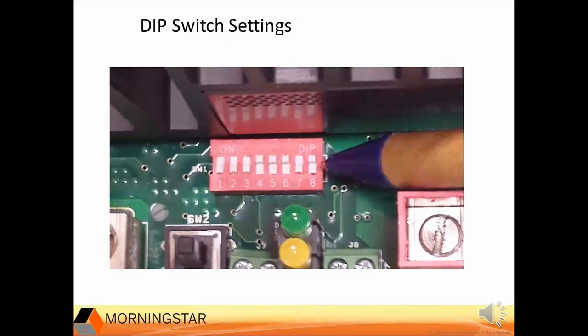Here are the eight DIP switches used to adjust the settings of the TriStar MPPT controller, used to enable certain settings of the controller. Here we have switches four, five, and six up to enable the custom settings once it's programmed, and switch eight up to enable writing the program settings to the controller with the Ethernet connection. If you have a serial connection, this is not required.